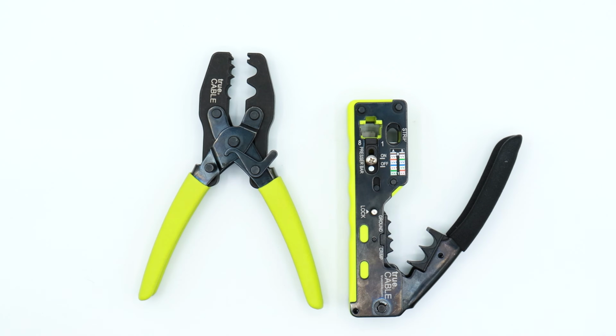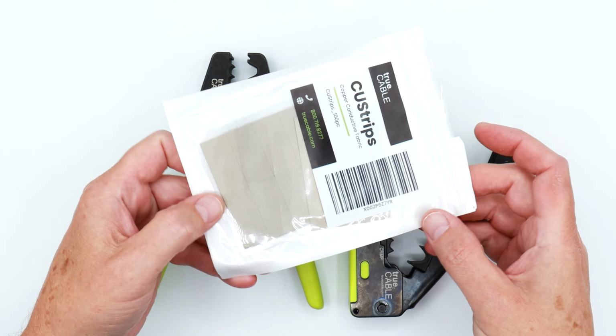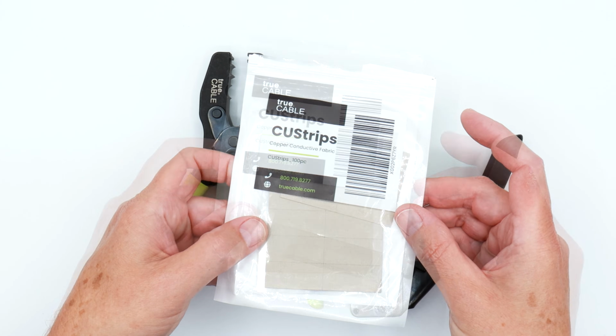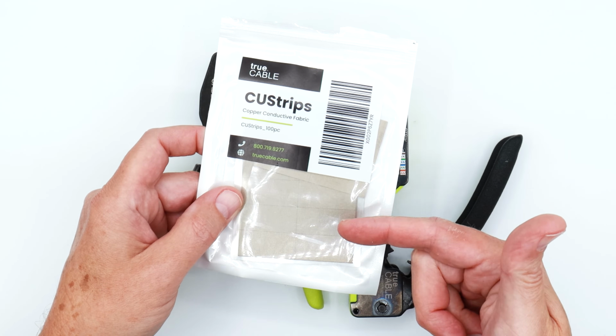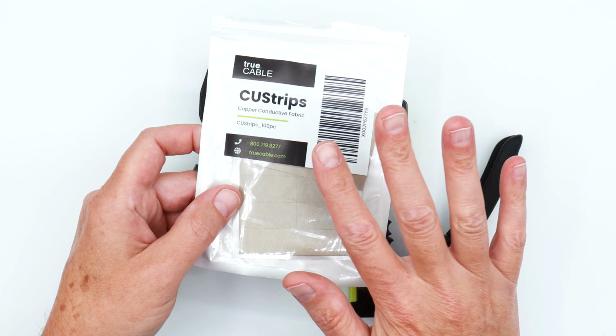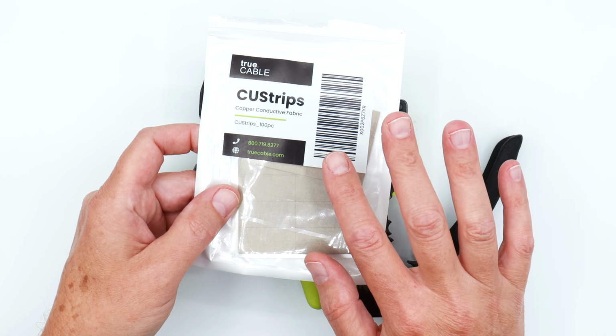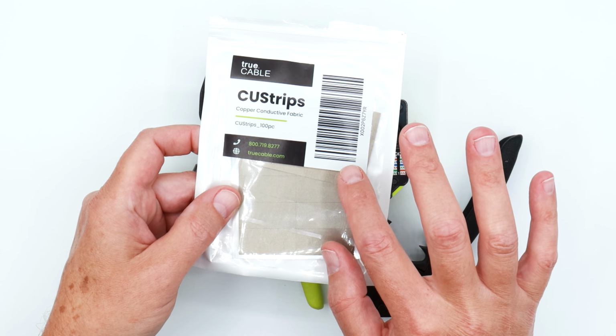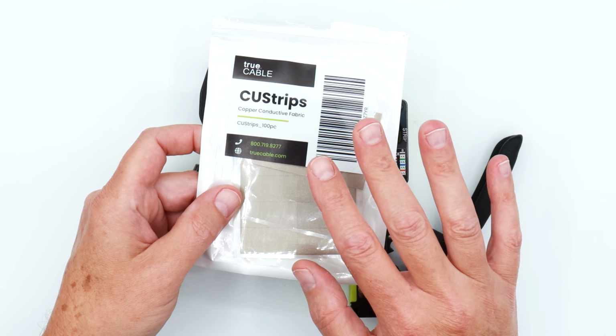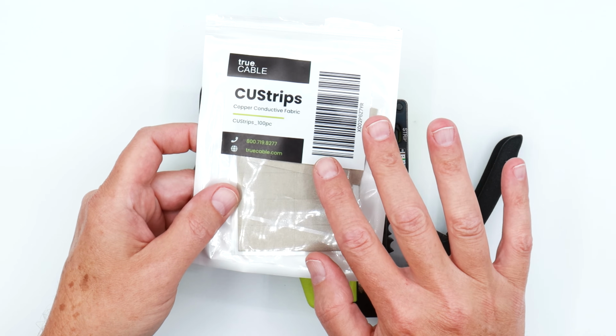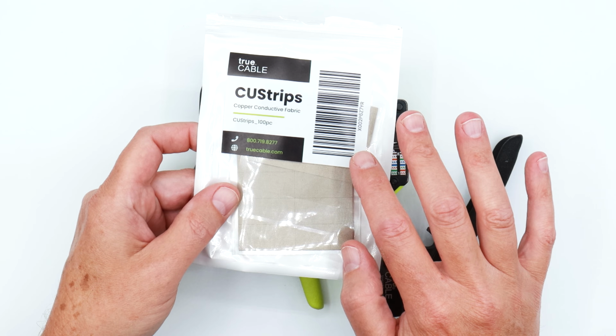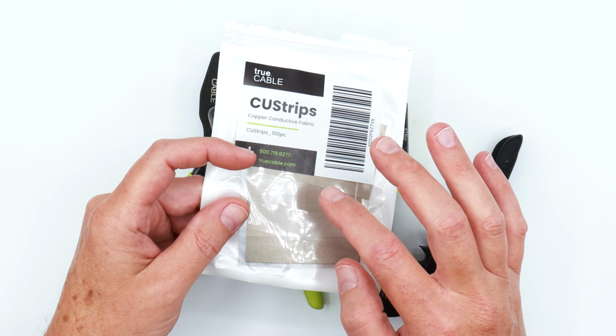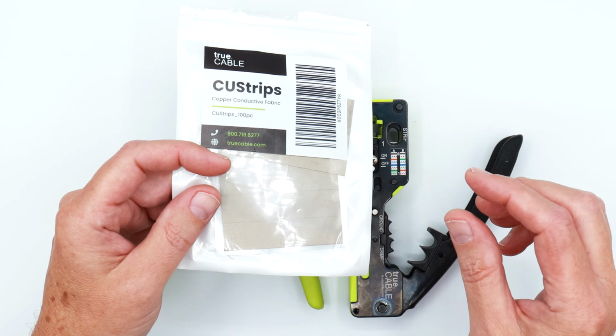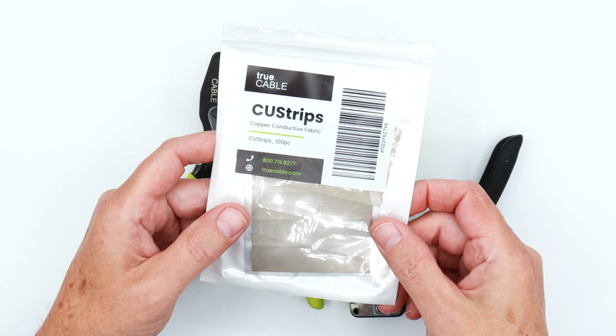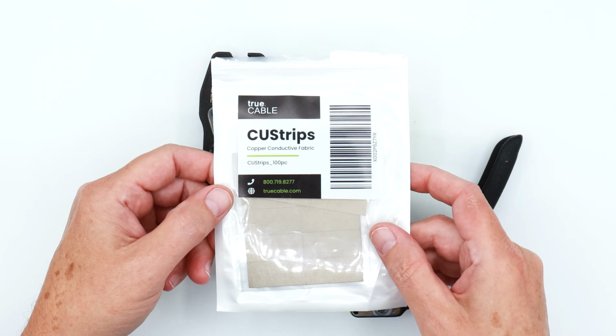Another thing that you're going to find very useful is our copper fabric strips. Now, these copper fabric strips function just like copper tape with a conductive adhesive, except these strips are very thin and they don't rip by mistake, which happens a lot with copper tape. So this eliminates the need to fold back the cable shield and then wrap the drain wire around that and try to jam it into the rear of the plug. So that's going to make bonding your cable shield a lot simpler.